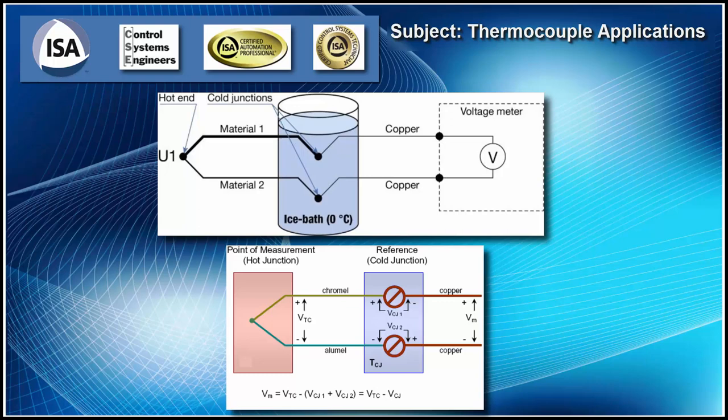Okay, with the thermocouple, this junction joined together produces a voltage and it's called the Seebeck effect. So whenever you have a junction, it actually is a small battery. And it actually generates millivolts. Instead of a big battery putting out volts, this puts out millivolts. So like at room temperature, you might have 1.5 or 2 millivolts. And whenever you have a junction, you create a battery.